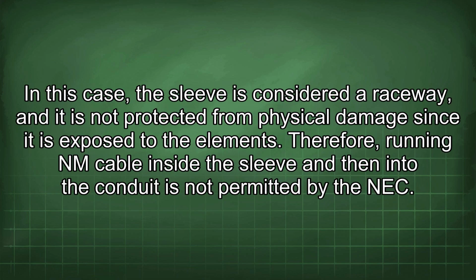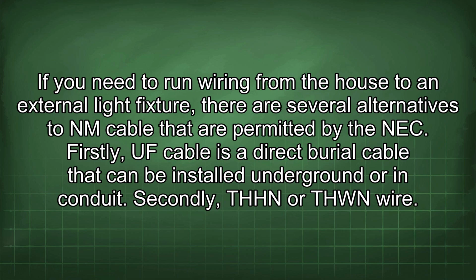In this case, the sleeve is considered a raceway, and it is not protected from physical damage since it is exposed to the elements. Therefore, running an NM cable inside the sleeve and then into the conduit is not permitted by the NEC. If you need to run wiring from the house to an external light fixture, there are several alternatives to NM cable that are permitted by the NEC.